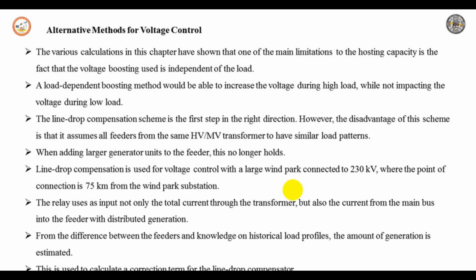However, the disadvantage of this scheme is that it assumes all the feeders from the same HV and MV transformer have a similar load pattern. So when adding a large generator unit to a feeder, this no longer holds. So consider line drop compensation used for voltage control with a large wind park that is connected to 230 kV, where the point of connection is 75 kilometers from the wind park substation.